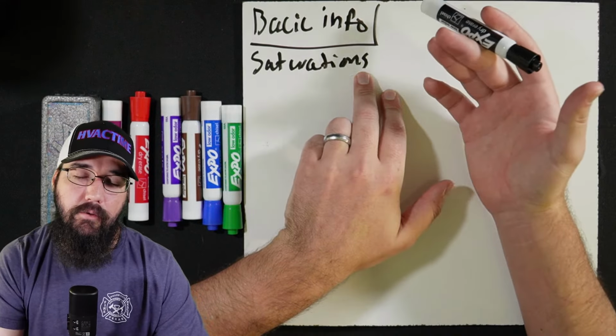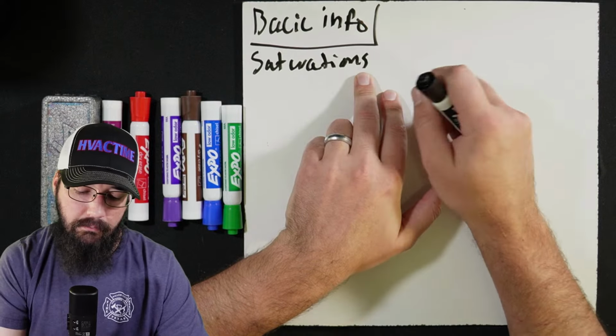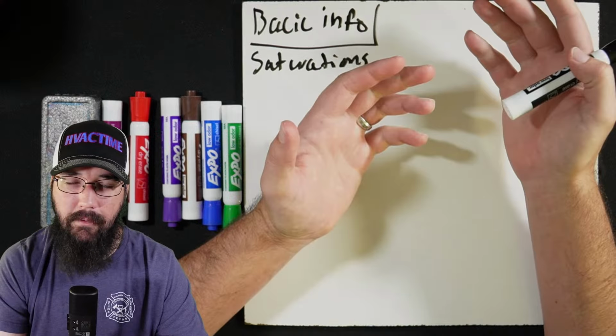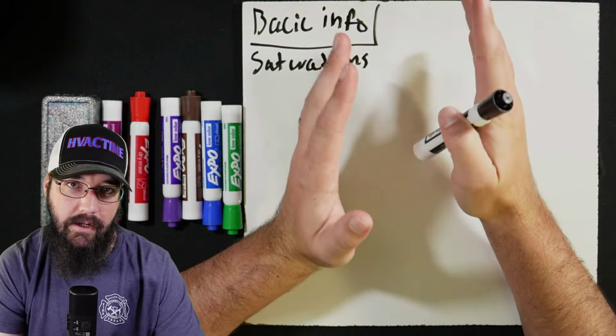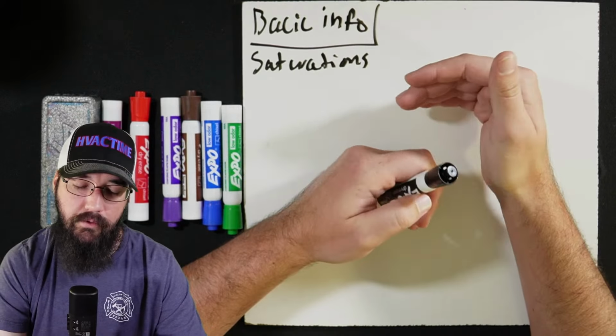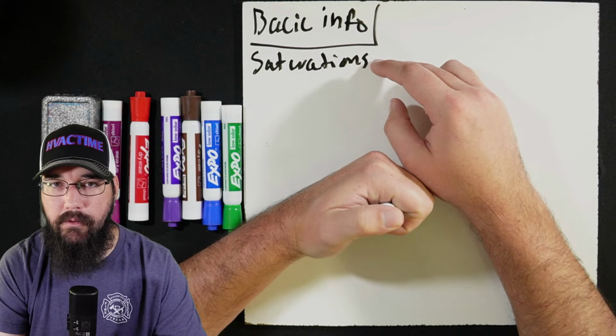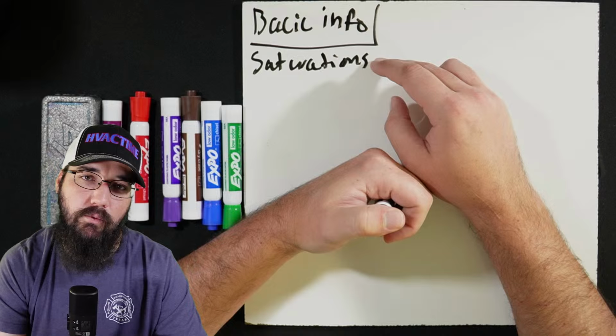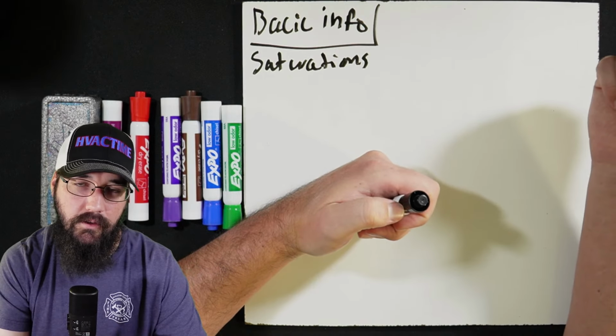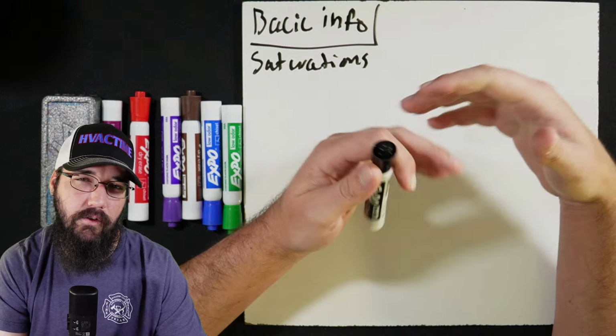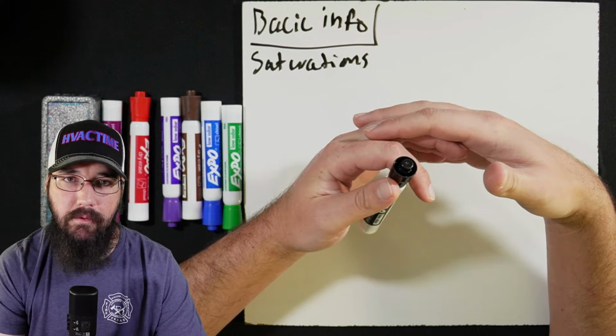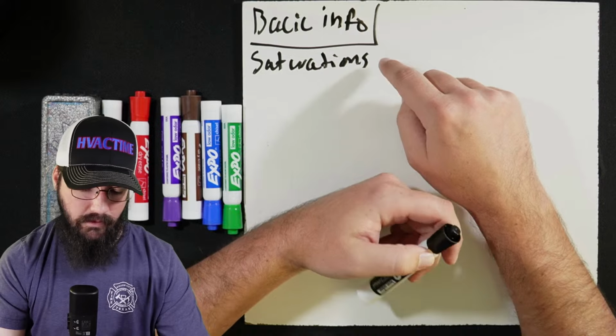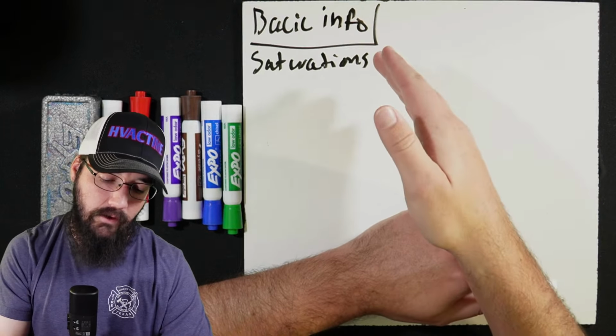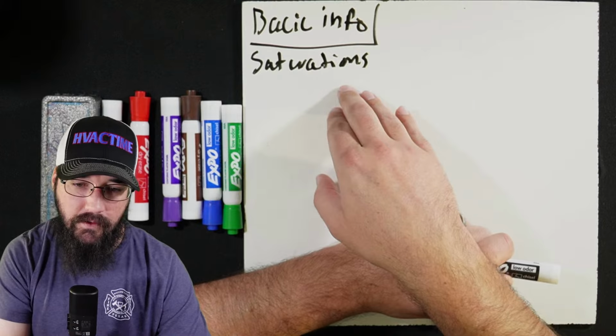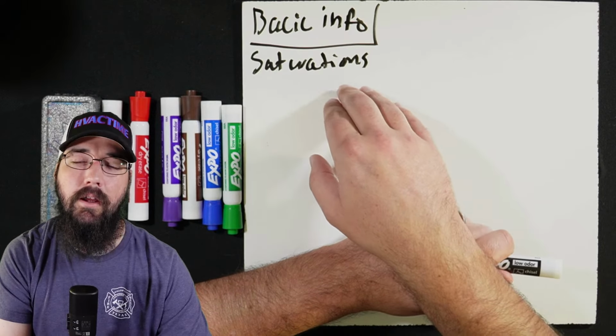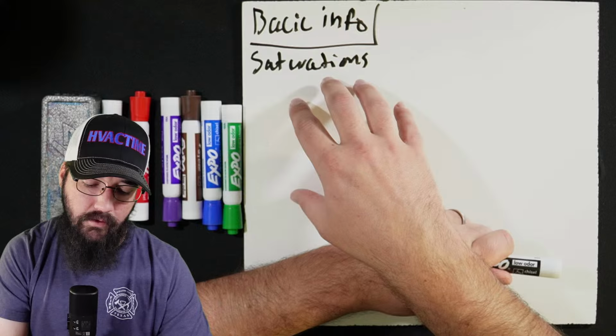So we need to dehumidify no longer applies. That's part of my point. If your understanding of saturation on the evaporator side is we need to dehumidify, and that's kind of the baseline of what you've built your understanding on, well, with the chiller circuit, the refrigerant itself is not dehumidifying. The water does in the coil, sure, but that's a different topic. They're connected, don't get me wrong. They're still connected, but this is a big topic. I hit this so heavily because in all my years of training this material, this has always consistently become a sticking point for so many people. So I hyper focus on that heavily.